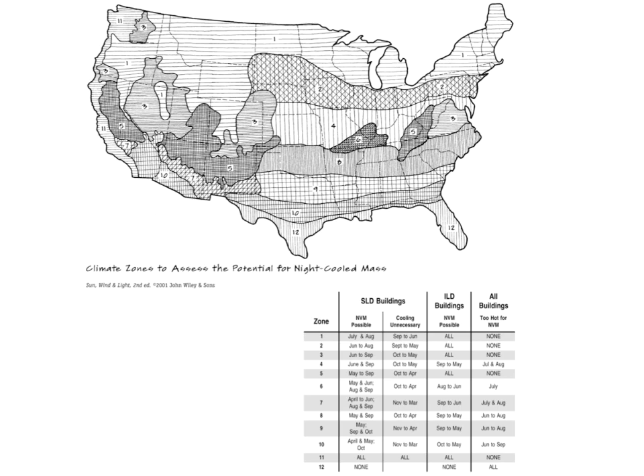Here's the sizing tool for night cooled mass. Now this is maybe one of the more complicated tools in the book, but we can break it down, and in the end it's not so complicated. So where we start with this is what we call the mass delta T. That is the temperature differential that's possible in the mass from its lowest temperature to its highest temperature across a 24-hour cycle.